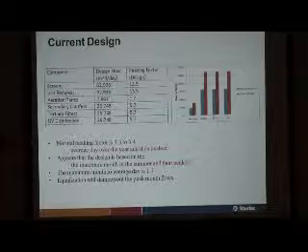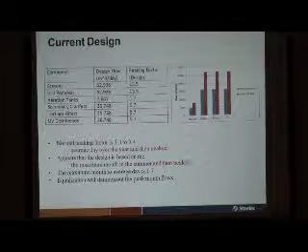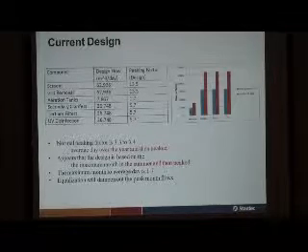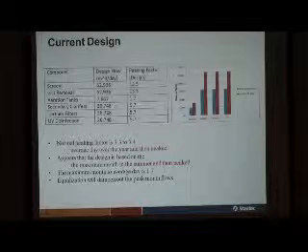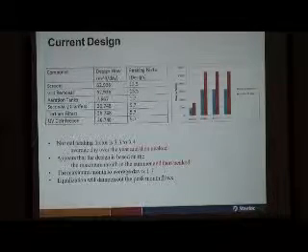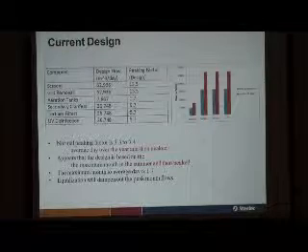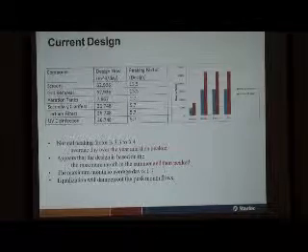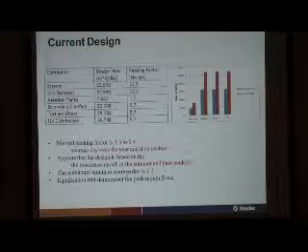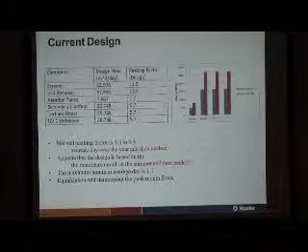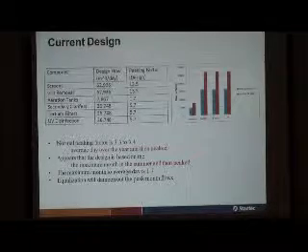So you can see by that little bar graph that there's quite a difference between using equalization. The blue bars are equalization, and the red is without equalization, the current design. So you can see that we can make things a lot smaller if we take advantage of one of those 4 lagoons for equalization.